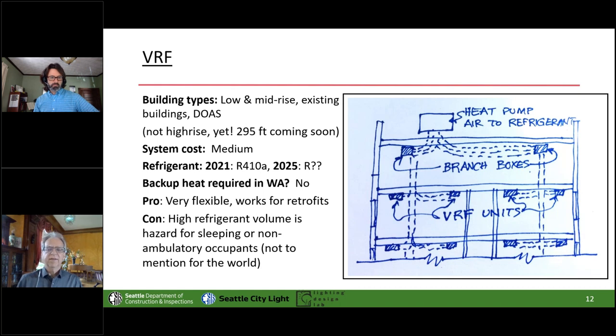Downside, if you count up all the refrigerant, even though those pipes are fairly skinny, that's an awful lot of refrigerant in there, and we'll talk about that more. But that's an increasing anxiety point for everybody: why are we doing all this energy efficiency if we're going to be filling buildings full of refrigerant that's going to be leaking out into the atmosphere? So there's the R410A and global warming potential. Duane's going to talk about that later.